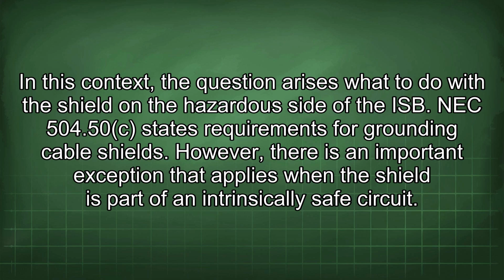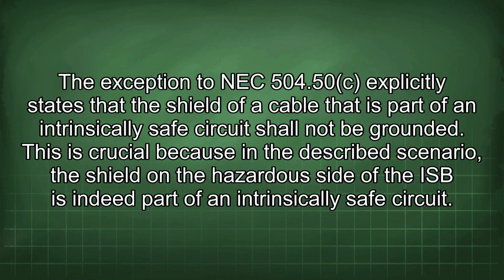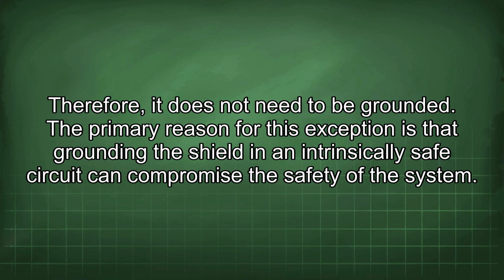NEC 504.50 states requirements for grounding cable shields. However, there is an important exception that applies when the shield is part of an intrinsically safe circuit. The exception to NEC 504.50 explicitly states that the shield of a cable that is part of an intrinsically safe circuit shall not be grounded. This is crucial because in the described scenario, the shield on the hazardous side of the ISB is indeed part of an intrinsically safe circuit. Therefore, it does not need to be grounded.